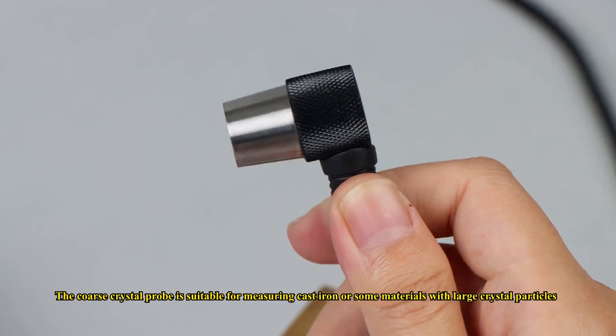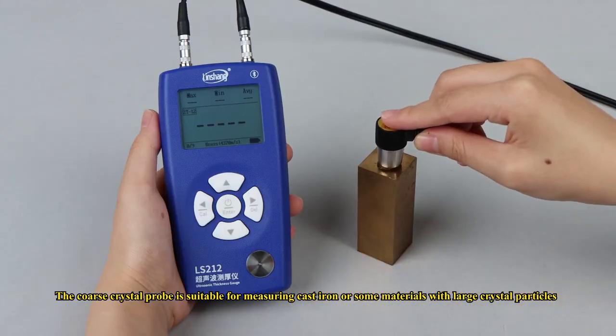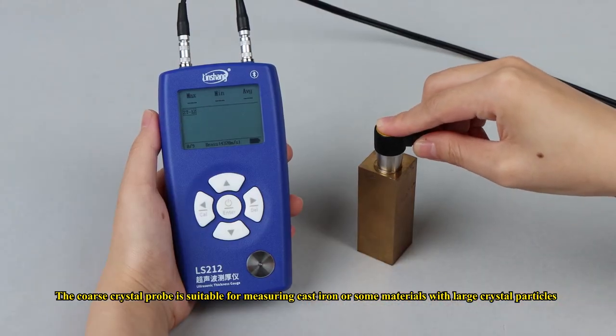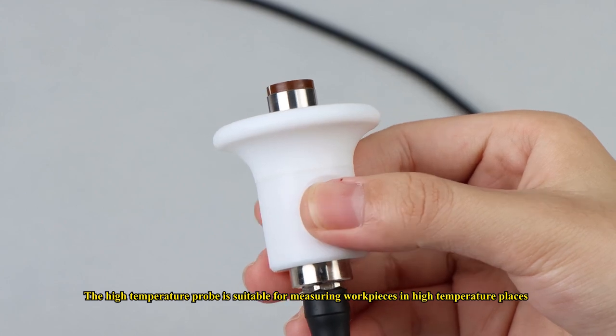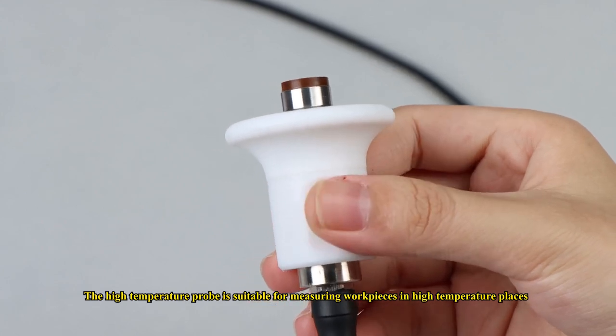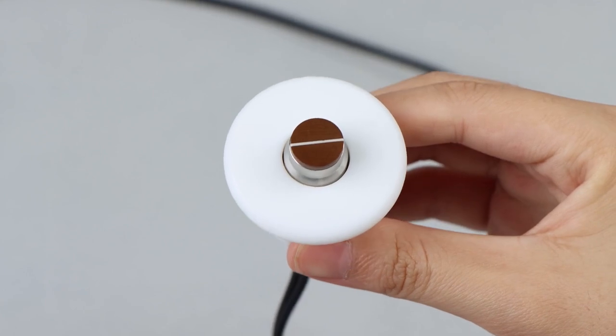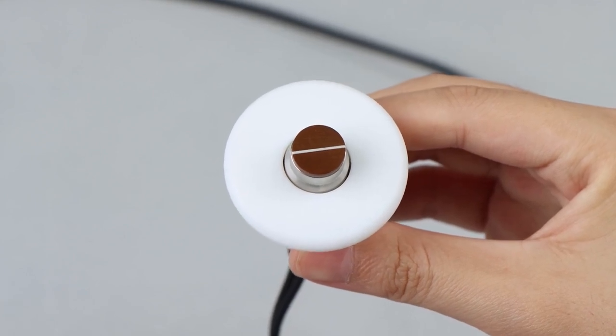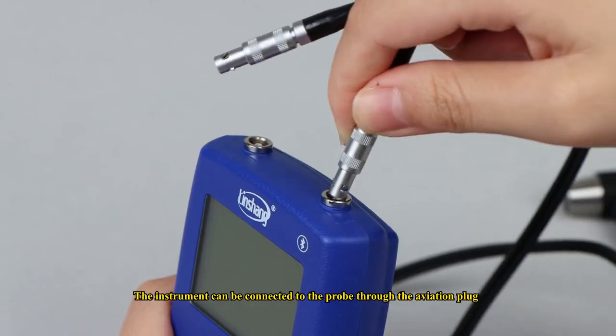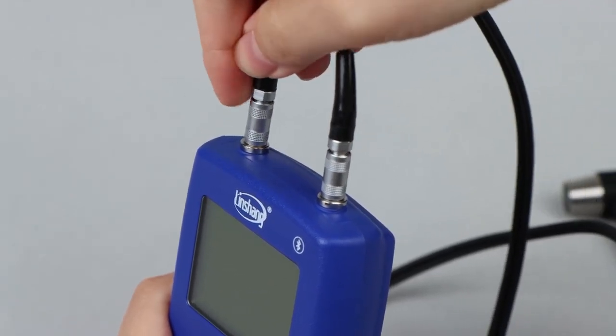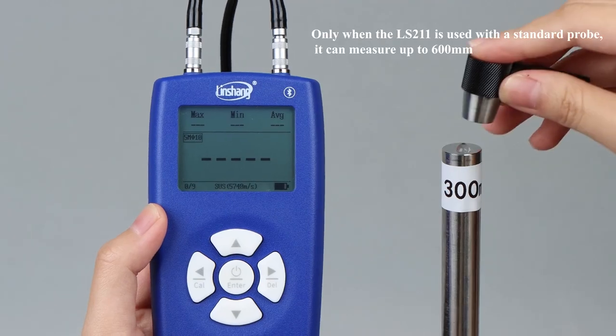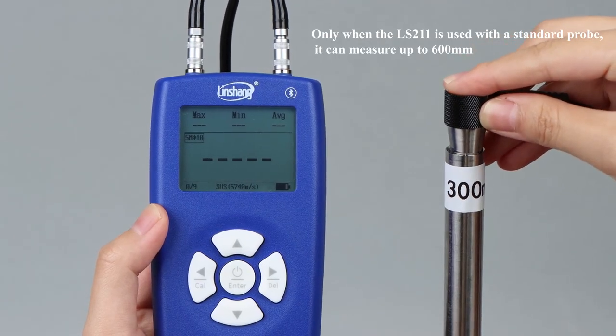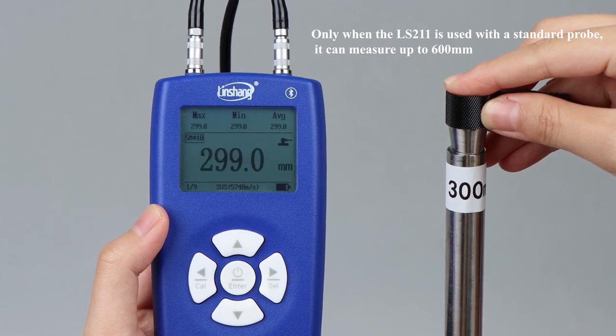The coarse crystal probe is suitable for measuring cast iron or some materials with large crystal particles. The high-temperature probe is suitable for measuring workpieces in high-temperature places. The instrument can be connected to the probe through the aviation plug. Linshang ultrasonic thickness gauge has a large range and can measure up to 600 mm.